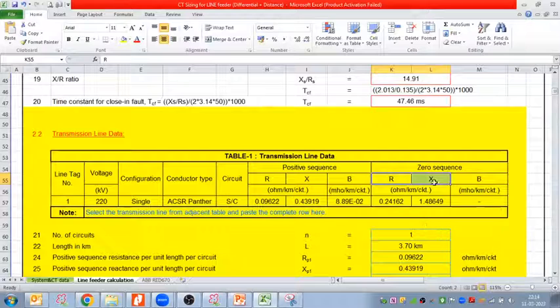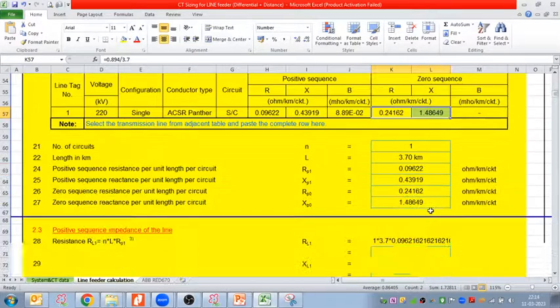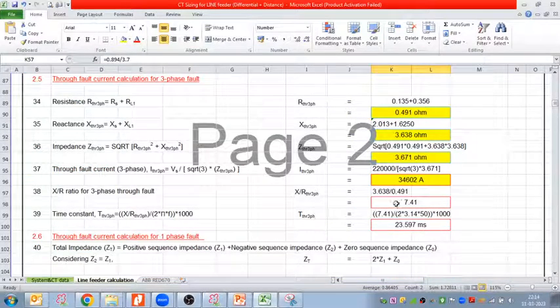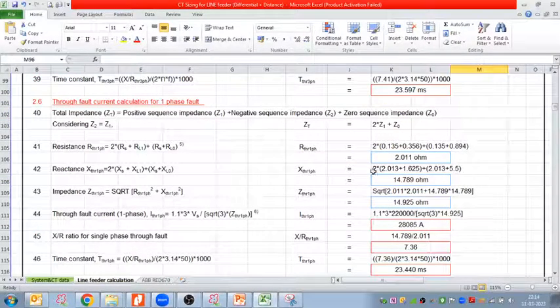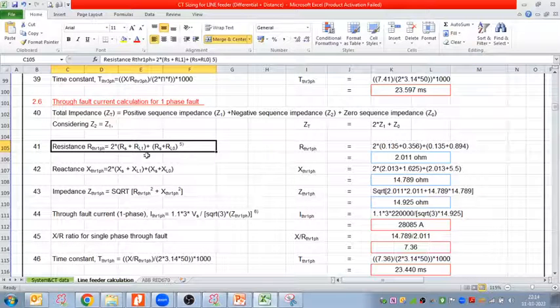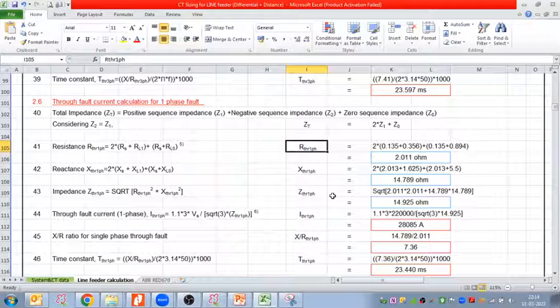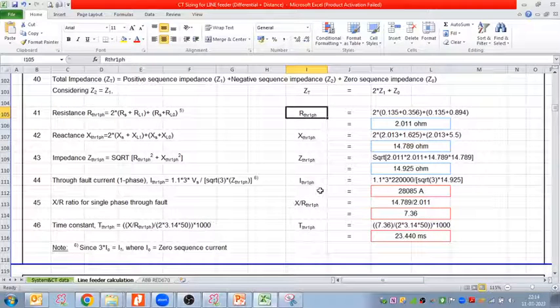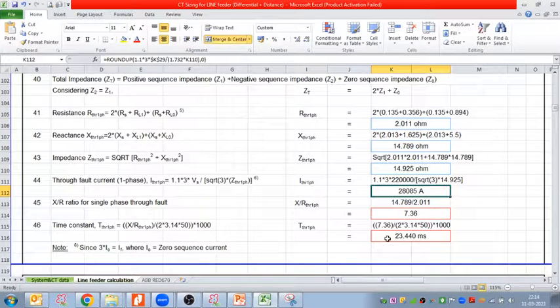If you see here, the zero sequence resistance and reactance values are higher than the positive sequence resistance and reactance. That's why the zero sequence impedance would be higher, and that's why the single phase fault current value will be lower, because impedance is higher. Just to show you, for the three phase fault we are getting 34.602 here. Now coming to the single phase fault, again we calculate the source resistance, but in this case we are using the zero sequence value. This fault current value comes to 28.085.